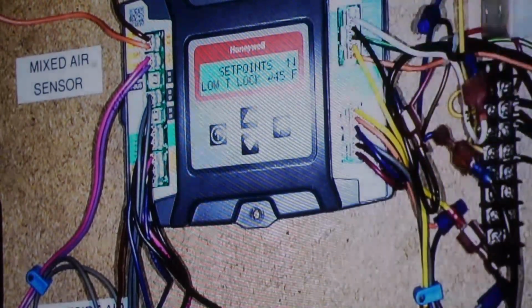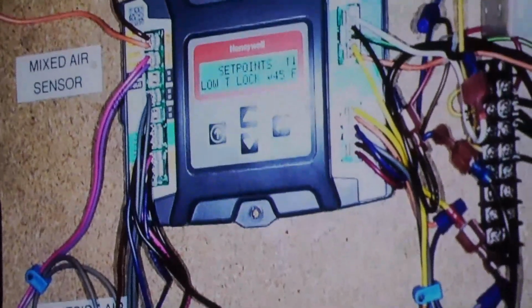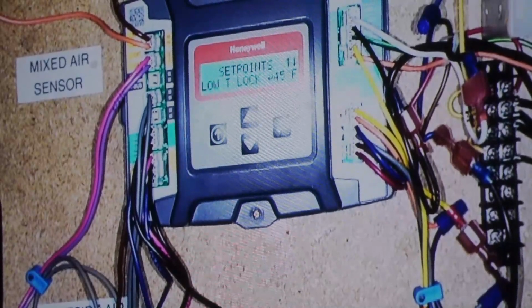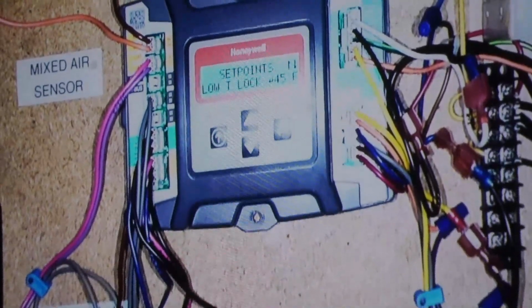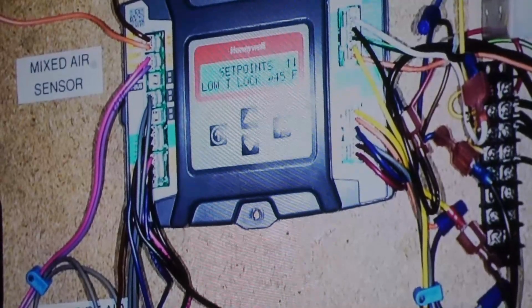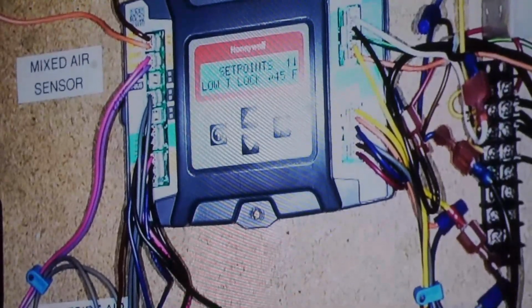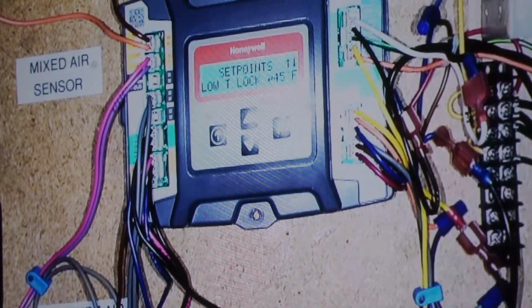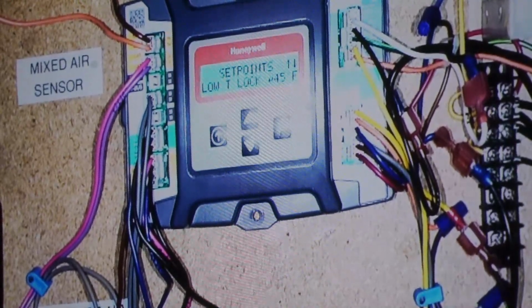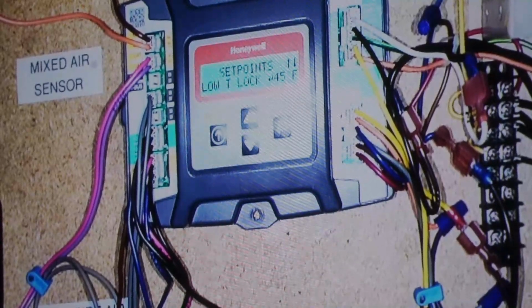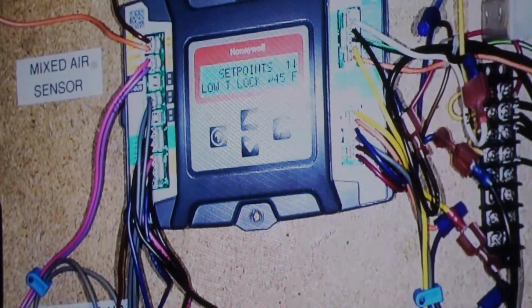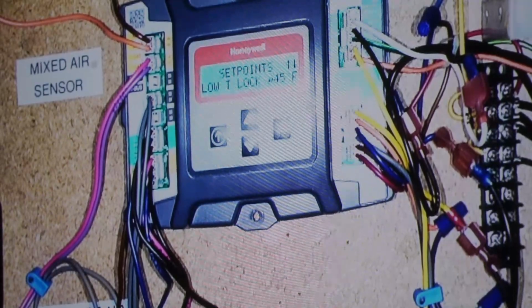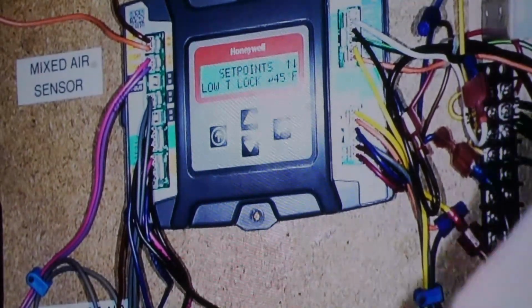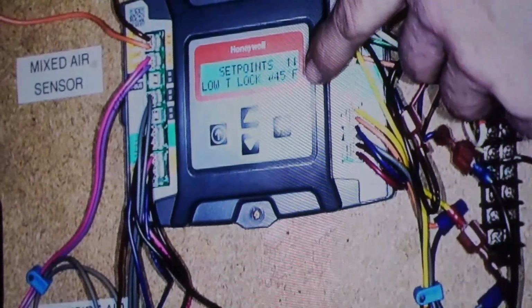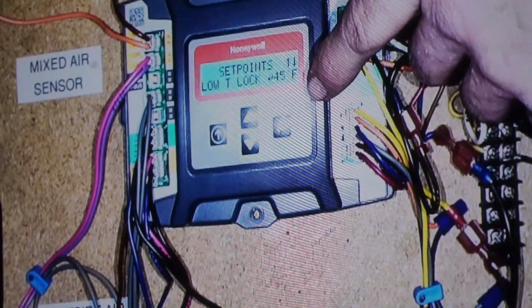Low limit lockout. Remember back in the day of our old economizers, we had Klixons, these guys. This is what locked out the refrigeration cycle before we put low ambient controls on it. So this was set at 45 degrees. We had another one of these maybe set at 55 for the economizer, so two of these. We're using that outside air sensor for everything. So make sure you change this back to 45 unless you have low ambient on the controller, on the unit. That's going to lock out refrigeration only.